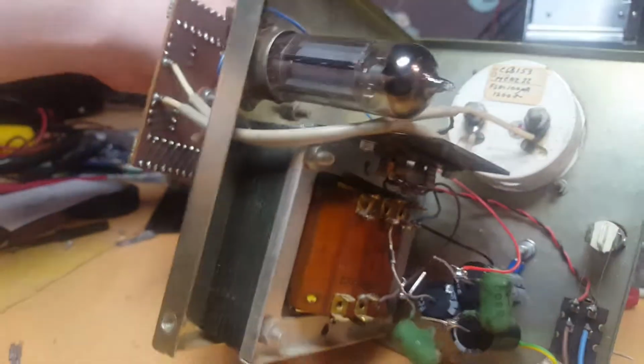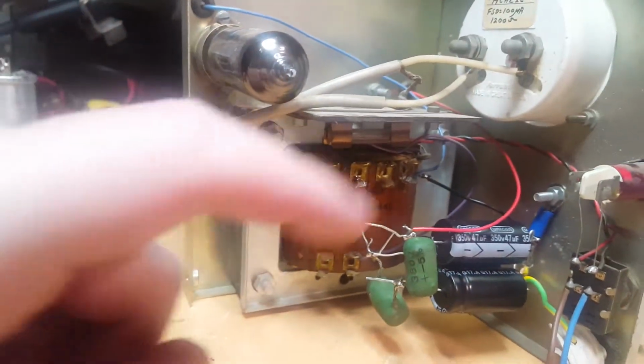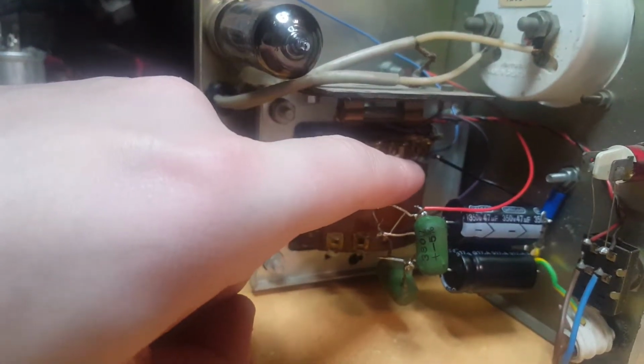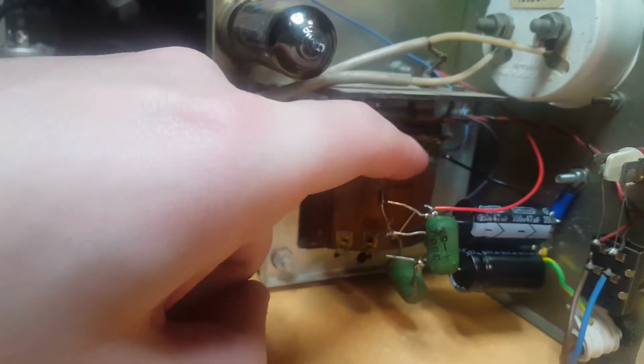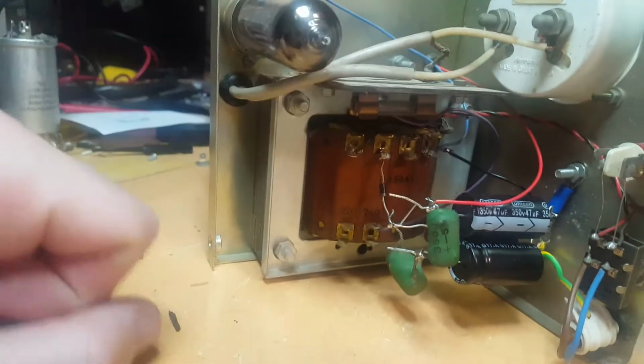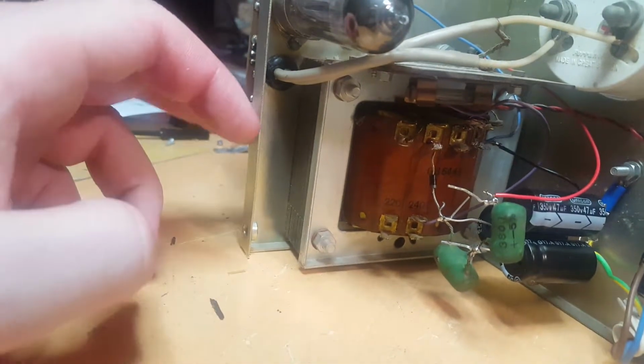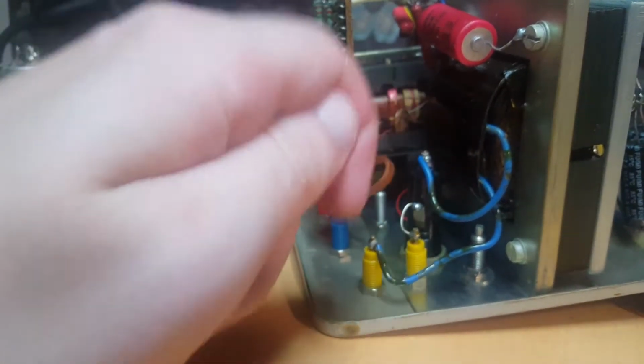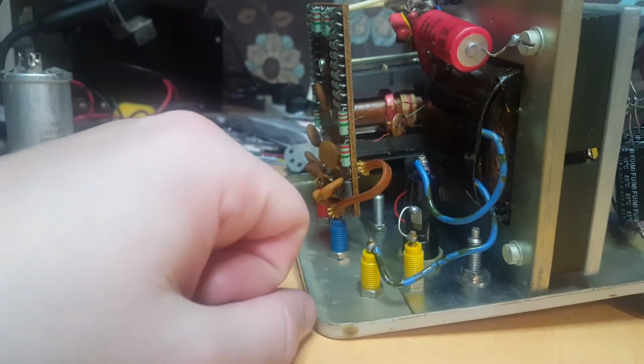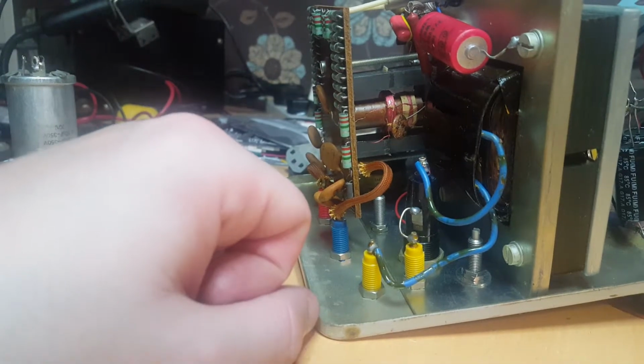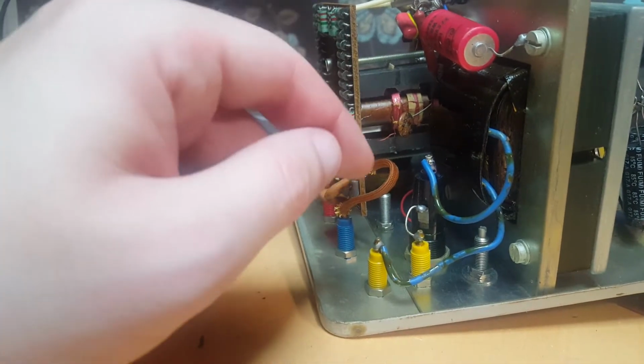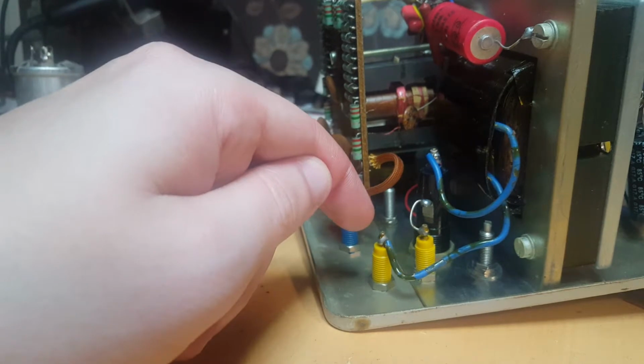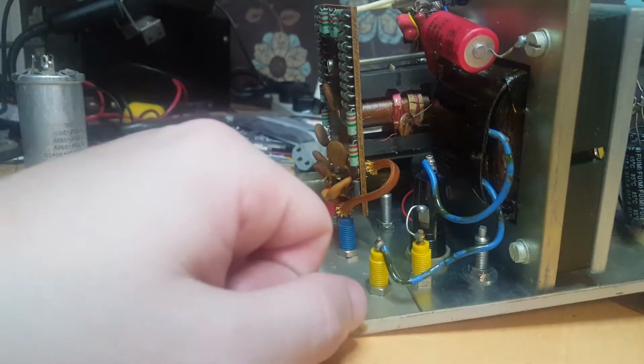The actual filament heater for this comes from a different place entirely - it's actually a winding on these two terminals. Yes, I have discharged these here and here. The easiest way to make sure there is absolutely no risk in the event of this transformer failing is simply to disconnect the auxiliary output. Although even if it did fail and somehow mains current made it to these and someone touched them, it's just going to trip the RCD.